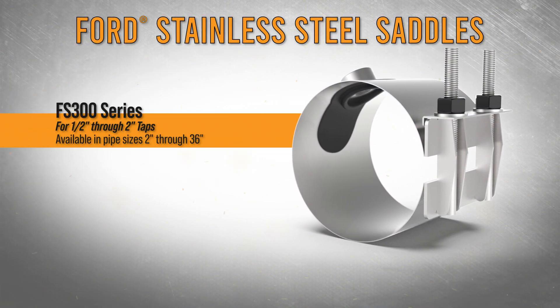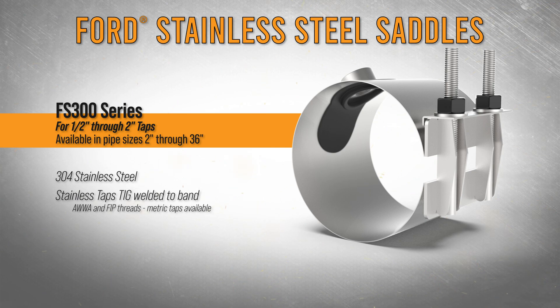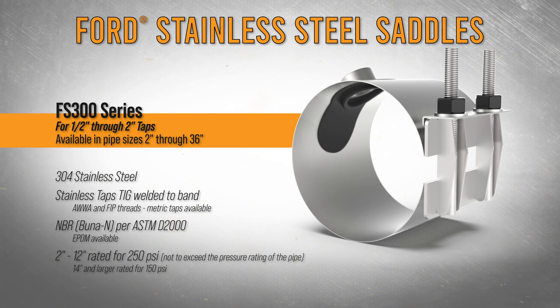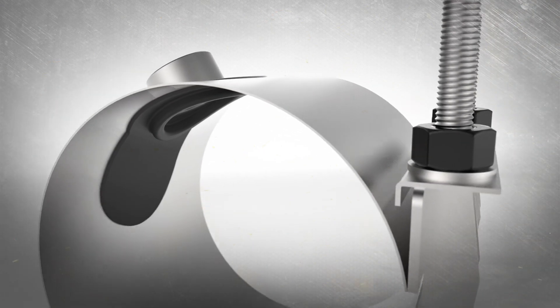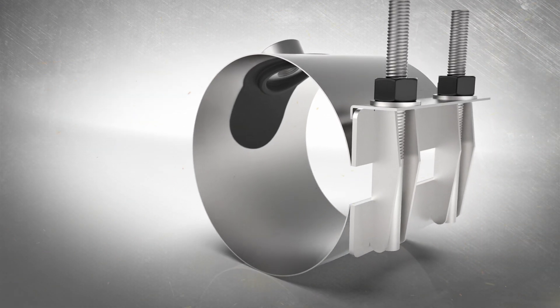The FS300 series is made of 304 stainless steel. Stainless taps are TIG welded to the band. BUNA-N or EPDM gaskets perform at a rated working pressure of up to 250 psi. Each saddle is fully passivated to withstand extreme conditions over a long period of time.